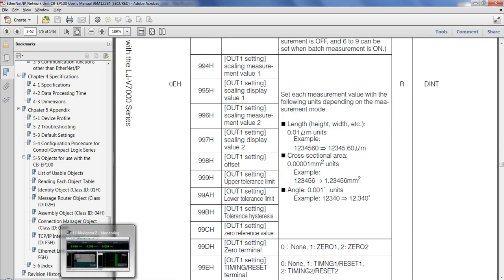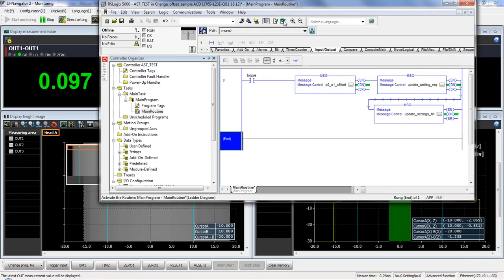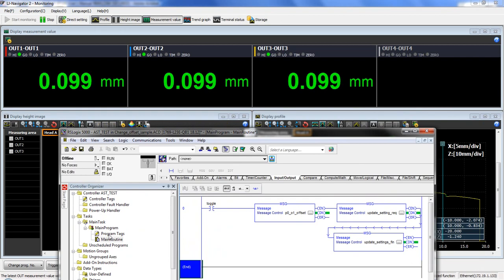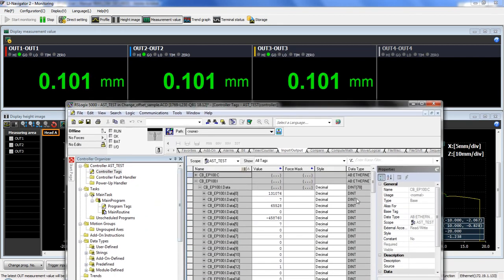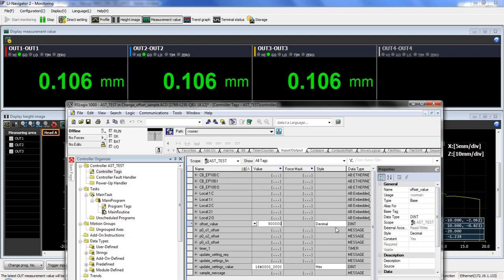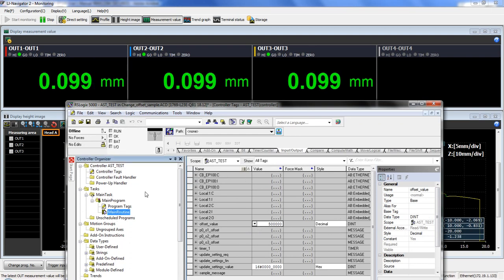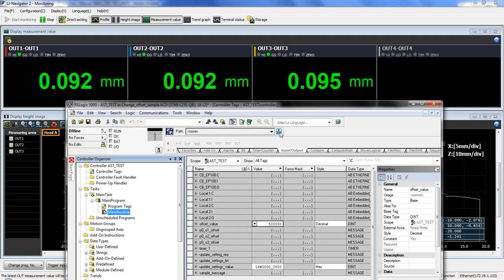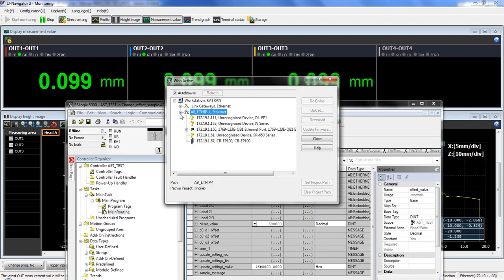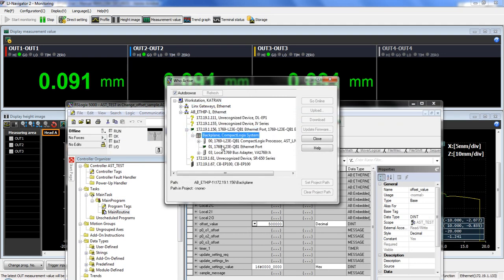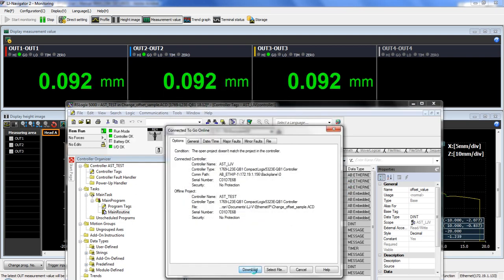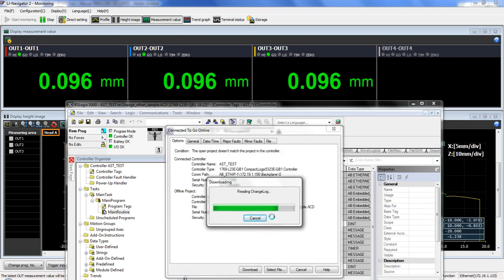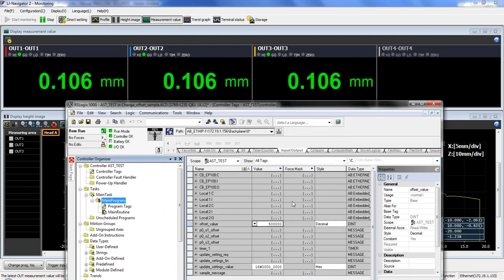So what we're going to do next is change the offset value. So this is the live screen here. What I've done here is I'm going to go to my controller tags, go to my offset value. I change that to 500,000. So that's going to correspond to 5. Remember, we divide by 100,000. And then I'm going to go here. Again, we're going to go online. Oh, sorry. I forgot to do this again. Go online. We're going to download this to the controller or a PLC again. Yes. Okay. So now we're online. Run mode. Everything's good. We see green.